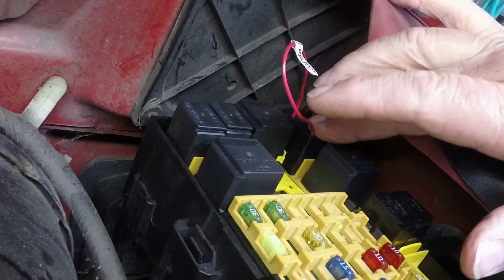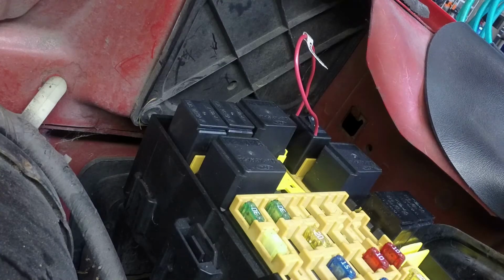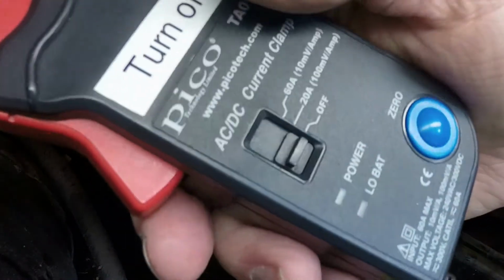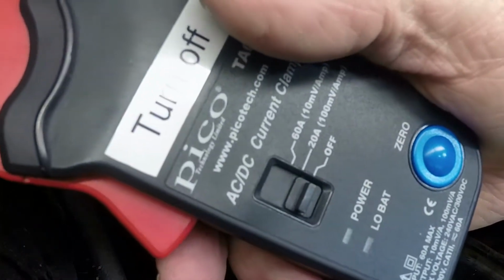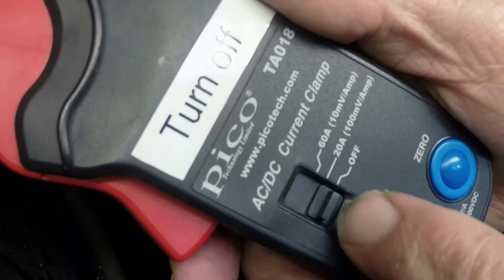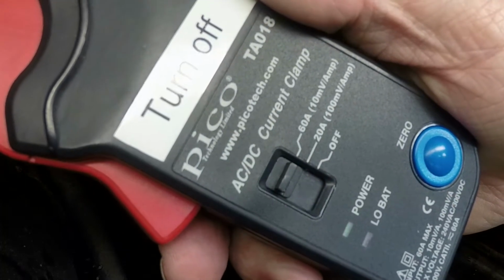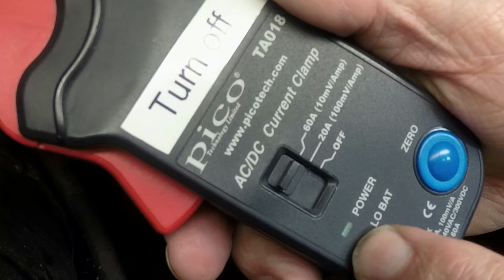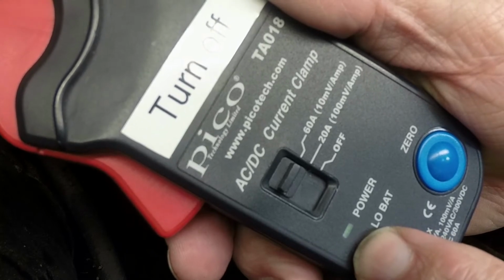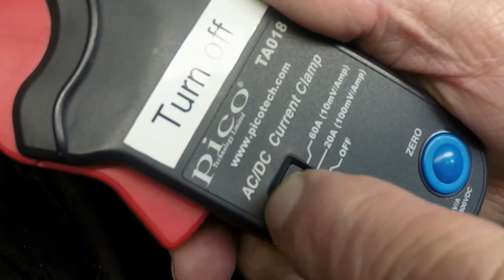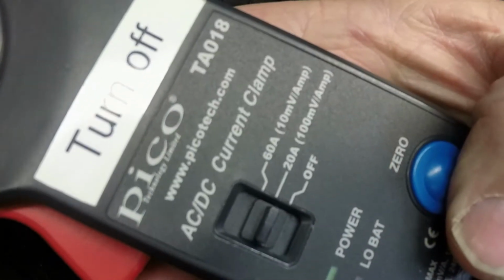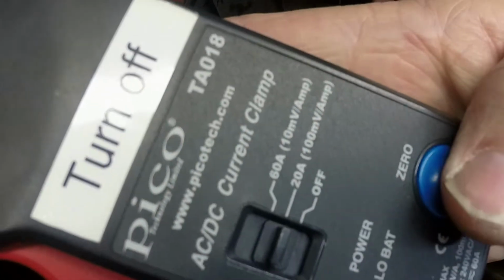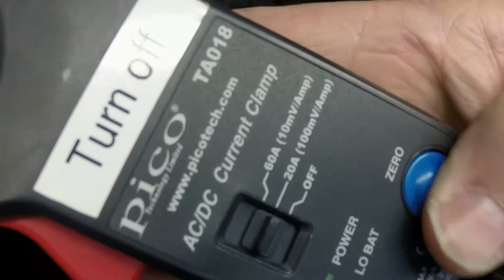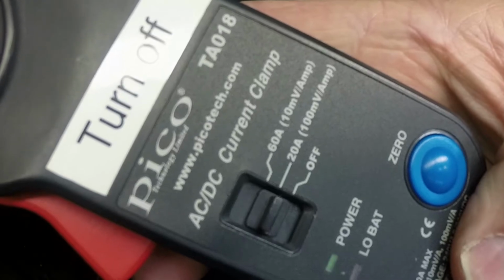So there it is, and now we'll hook up the amp clamp. When you hook the amp clamp up, there's a setting right here. You flip this on, and there should be a battery light that shows up, and it should be green. Once you turn it on, we're going to read the 20 amp scale, so we're going to bring it down to 20 amps. Before you clip it onto the wire, press and hold the 0 button for a second or two, and that zeroes out the amp clamp. So now it's ready to go.